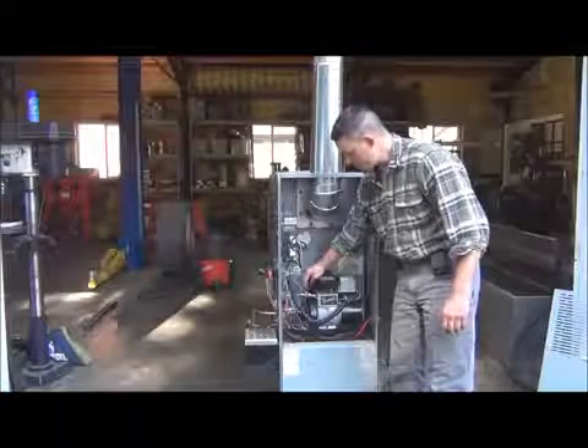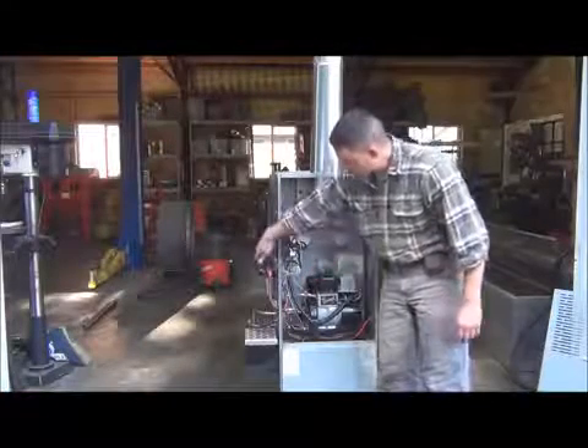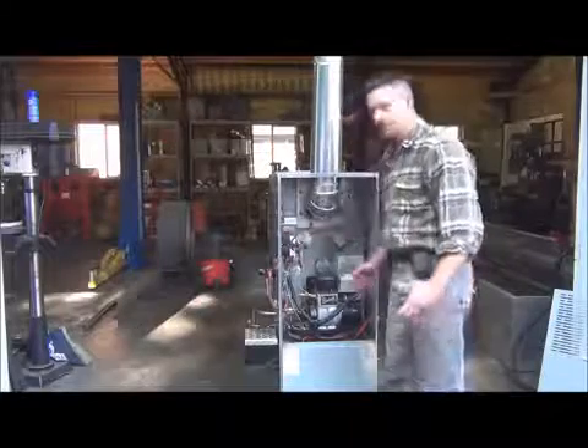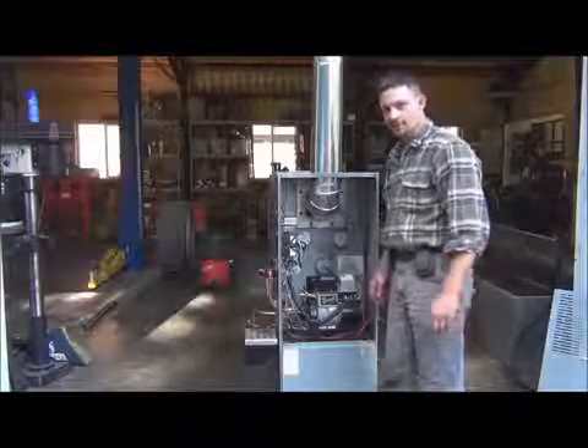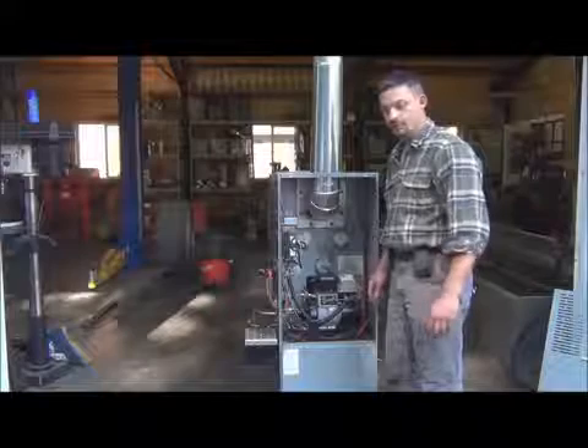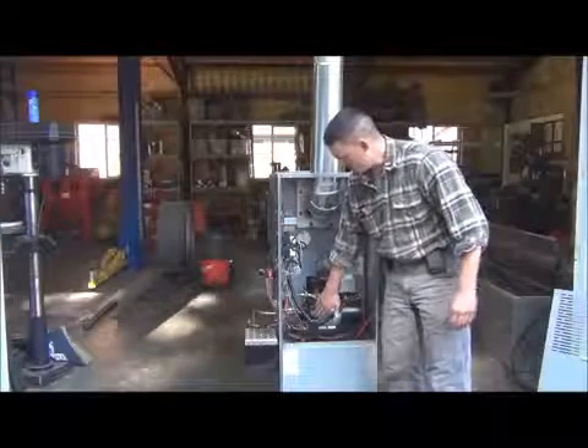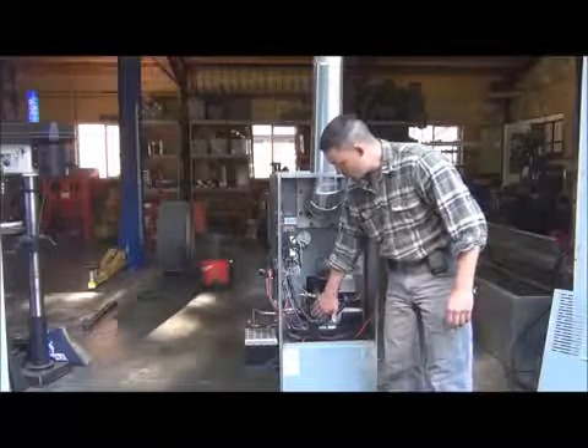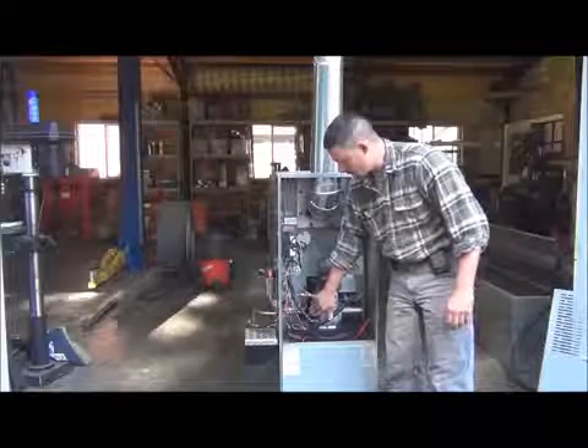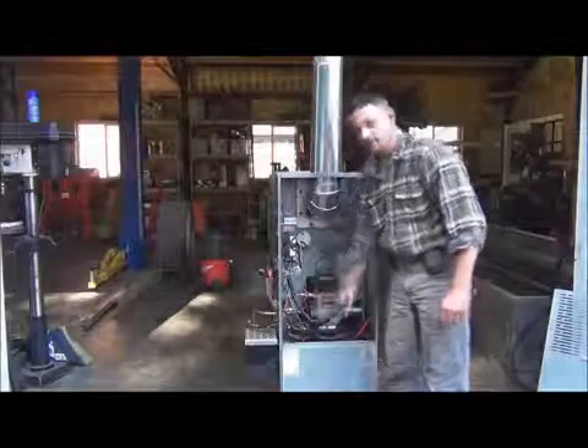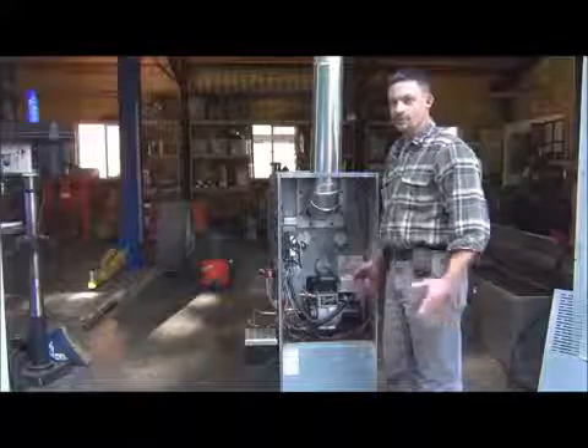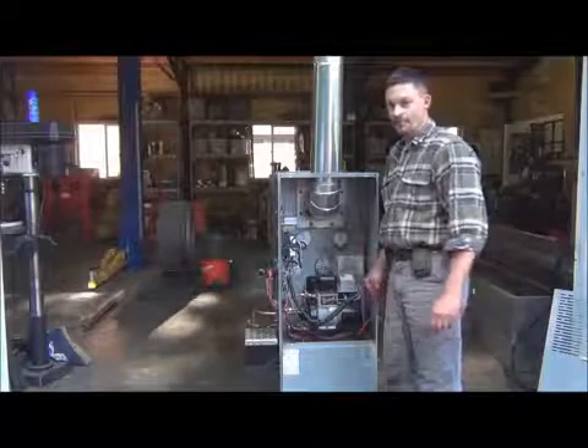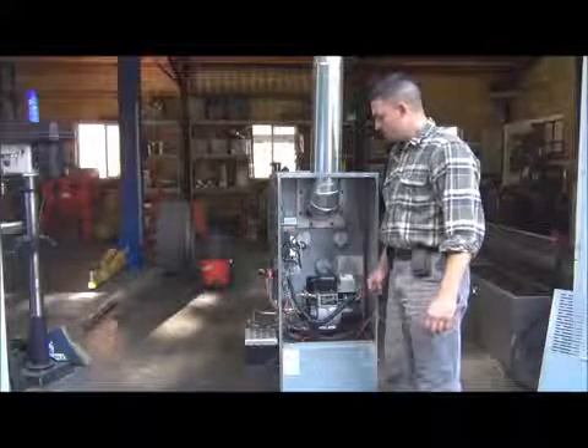I adjust the fuel flow rate based on the pressure regulator out here. The higher the pressure, the more suction it develops, and the more oil it actually sprays into the combustion chamber. And then I adjust my air with the pump's air valves right here. So I can adjust my fuel-air ratio pretty easily based on the type of fuel that I'm burning or how hot I want it to burn.